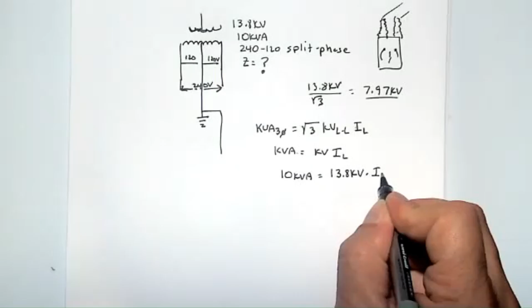So we'd have 10 kVA. I equals 10 divided by the voltage, 13.8. So 10 divided by 13.8, and right away we can see that's less than 1 amp. It's 0.725 amps. That's what's kind of cool if you think about it. They could use almost an Ethernet cable to feed your house. It's very low gauge wire, which is why they can use a 10 or 12 gauge wire uninsulated in the air, just feeding the primary.